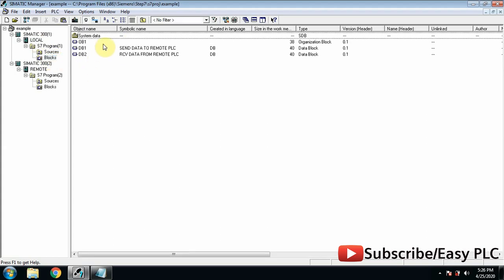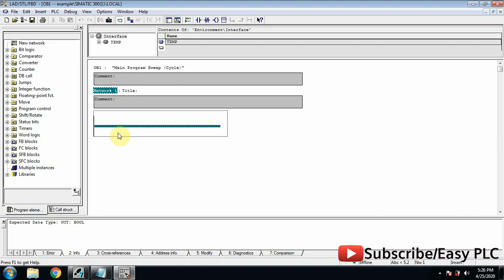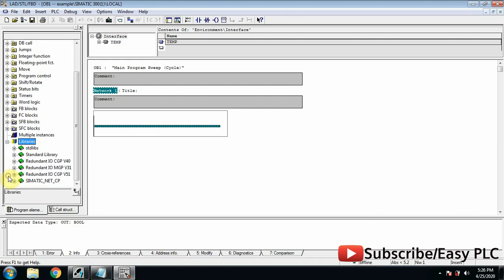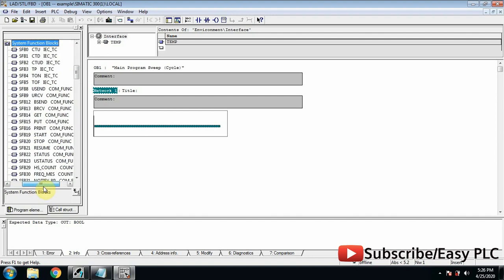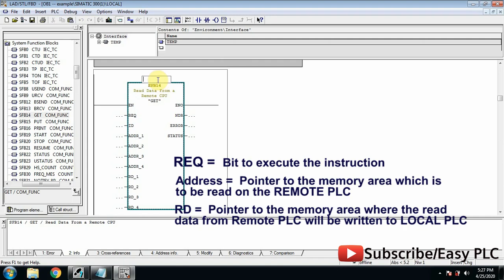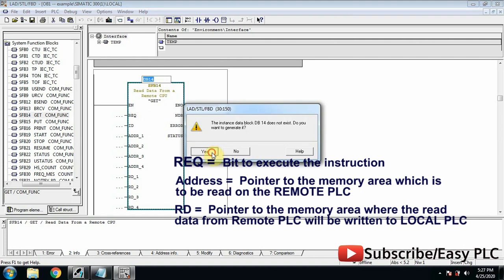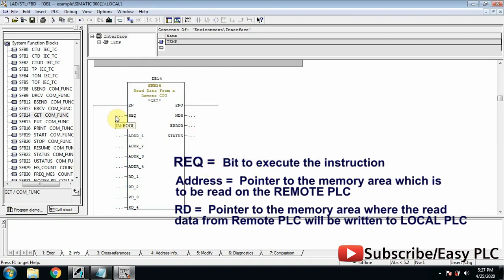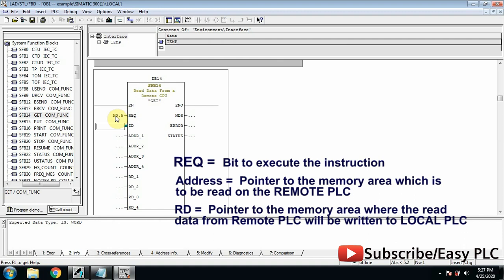Now we will go to organization block OB1 of the local PLC. Drag and drop the GET function on the ladder. The GET function will be used to read data from the remote PLC. This function needs a data block to operate — we will assign DB14 for the GET function. The Request input executes the GET function whenever this input signal goes from low to high; we will use clock memory bit M0.5.